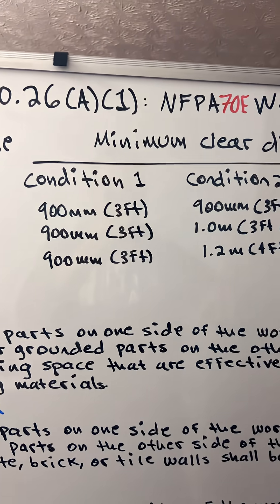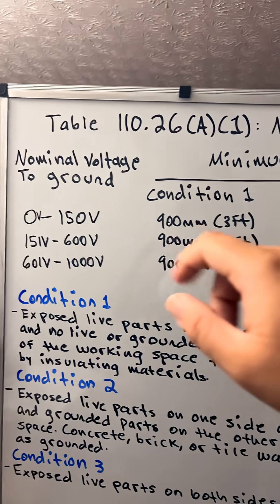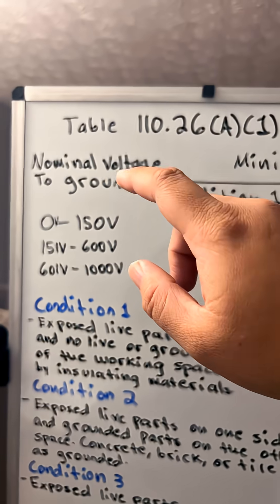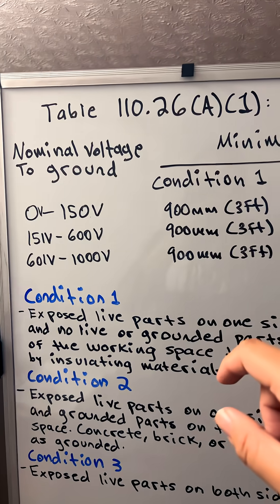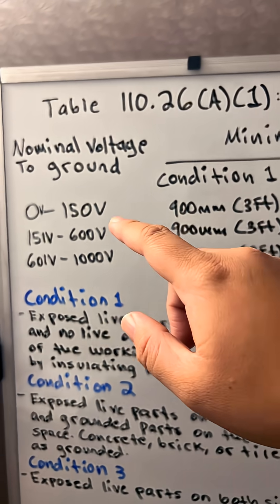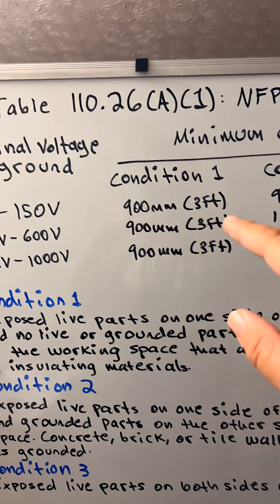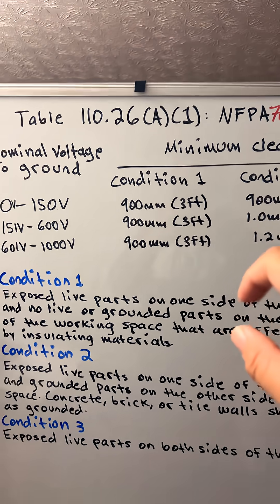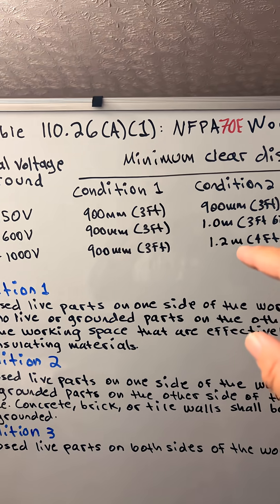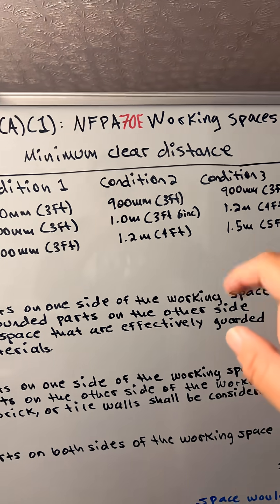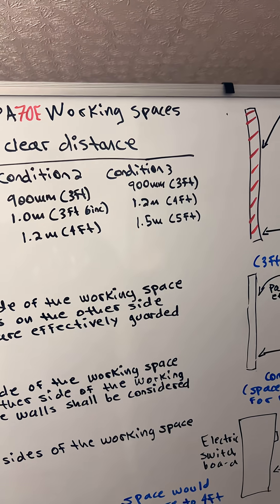As you can see here in the table, for the nominal voltage to ground from 0 volts to 150 volts: condition 1 is 3 feet, condition 2 is 3 feet, and condition 3 is 3 feet.